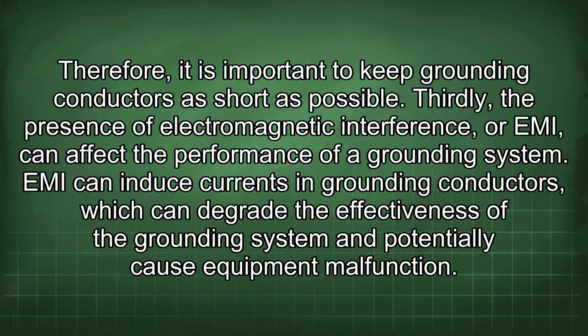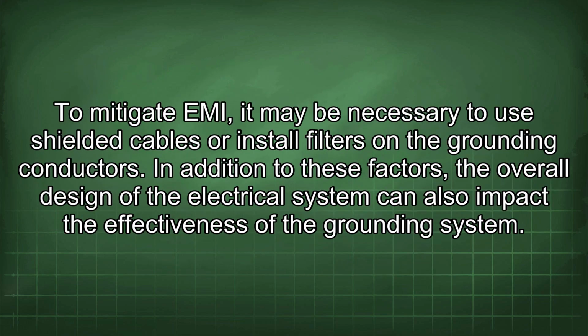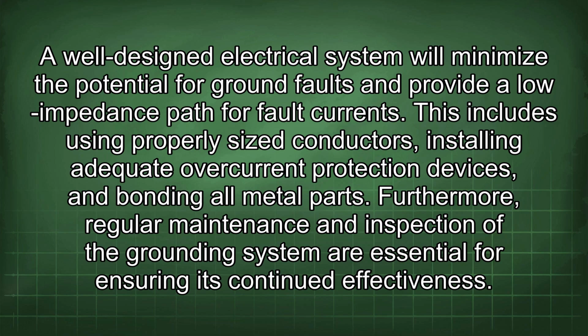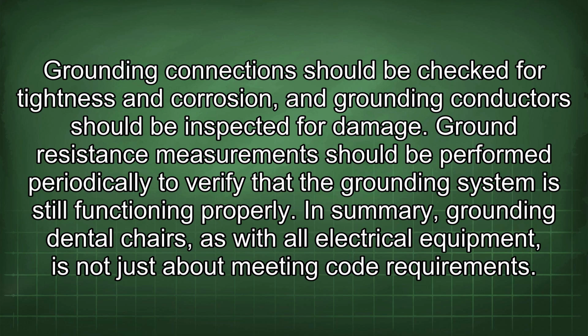Thirdly, the presence of electromagnetic interference, or EMI, can affect the performance of a grounding system. EMI can induce currents in grounding conductors, which can degrade the effectiveness of the grounding system and potentially cause equipment malfunction. To mitigate EMI, it may be necessary to use shielded cables or install filters on the grounding conductors. In addition to these factors, the overall design of the electrical system can also impact the effectiveness of the grounding system. A well-designed electrical system will minimize the potential for ground faults and provide a lower impedance path for fault currents. This includes using properly sized conductors, installing adequate overcurrent protection devices, and bonding all metal parts. Furthermore, regular maintenance and inspection of the grounding system are essential for ensuring its continued effectiveness. Grounding connections should be checked for tightness and corrosion, and grounding conductors should be inspected for damage. Ground resistance measurement should be performed periodically to verify that the grounding system is still functioning properly.